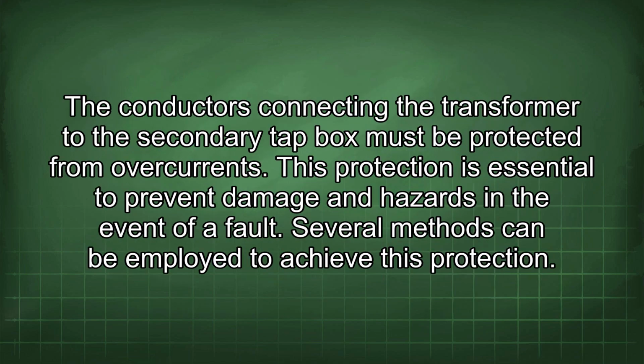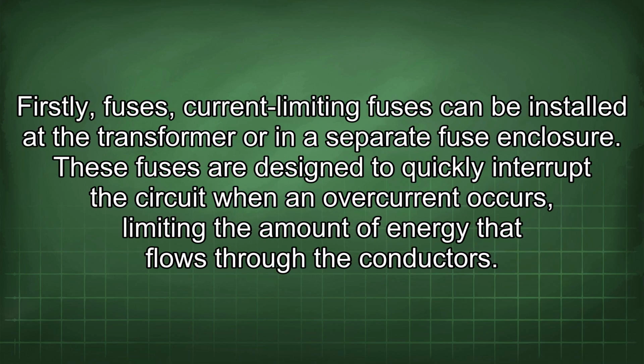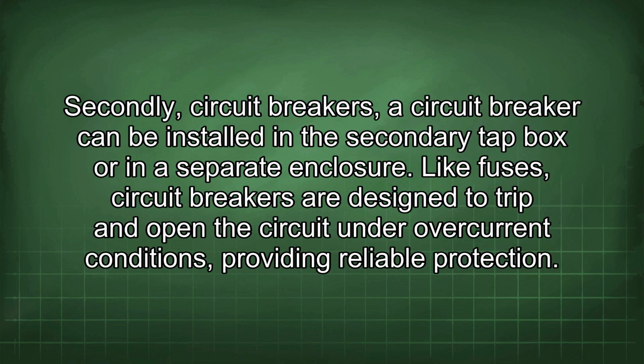These boxes provide a convenient and safe way to extend secondary services. The conductors connecting the transformer to the secondary tap box must be protected from overcurrents. This protection is essential to prevent damage and hazards in the event of a fault. Several methods can be employed to achieve this protection. Firstly, fuses. Current-limiting fuses can be installed at the transformer or in a separate fuse enclosure. These fuses are designed to quickly interrupt the circuit when an overcurrent occurs, limiting the amount of energy that flows through the conductors. Secondly, circuit breakers.